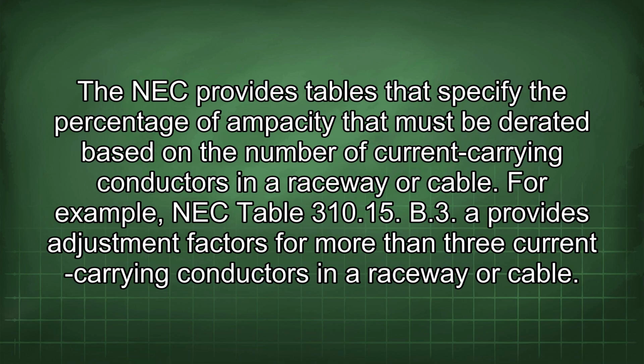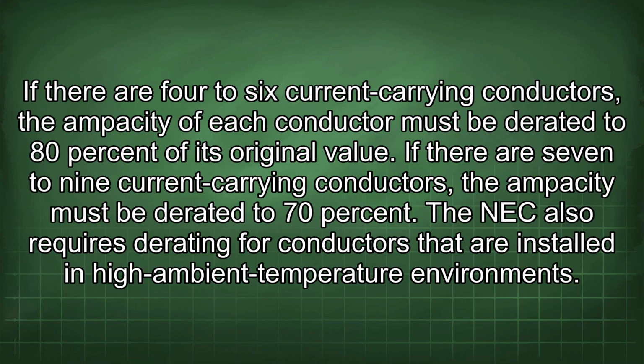For example, NEC Table 310.15(B)(3)(a) provides adjustment factors for more than 3 current carrying conductors in a raceway or cable. If there are 4 to 6 current carrying conductors, the ampacity of each conductor must be derated to 80% of its original value. If there are 7 to 9 current carrying conductors, the ampacity must be derated to 70%.